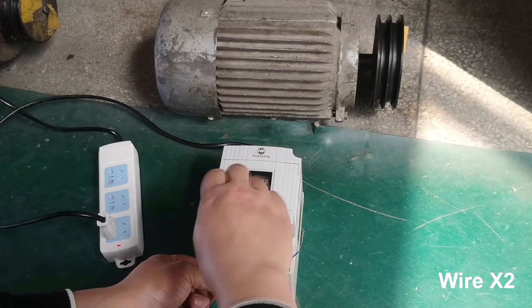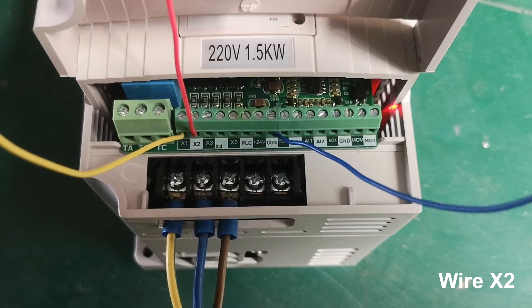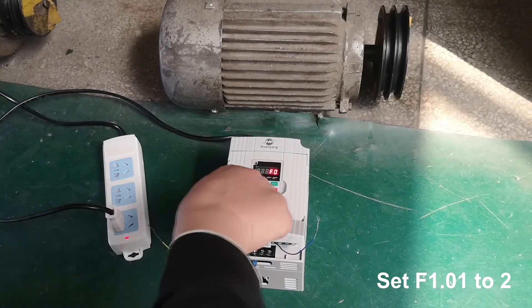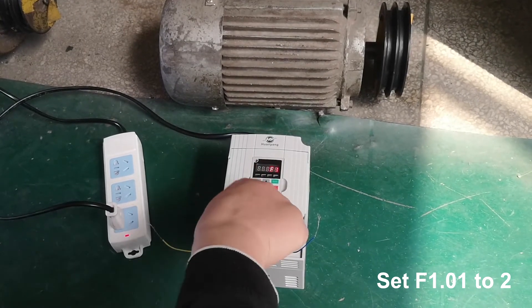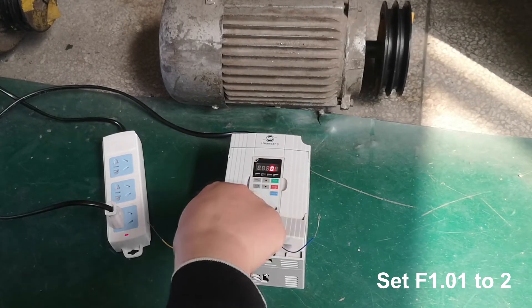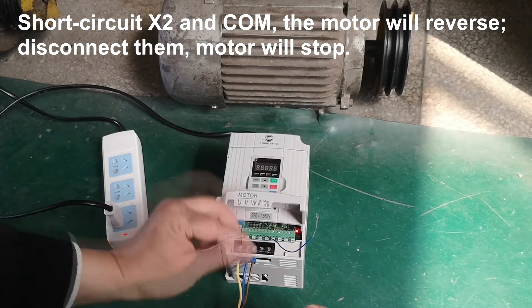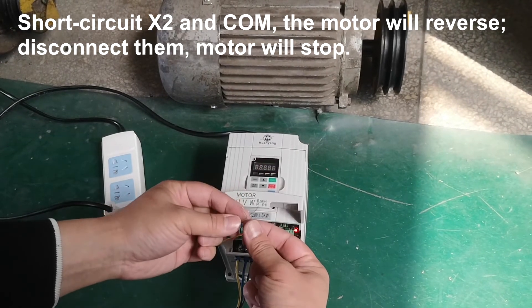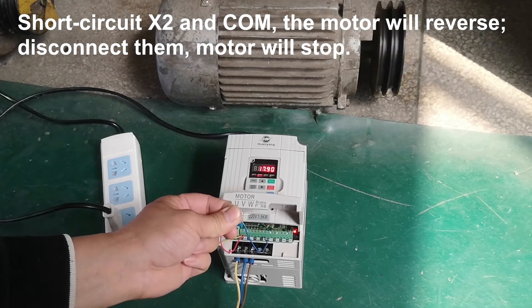Wire X2. Set F1.01 to 2. Short circuit X2 and COM — the motor will reverse. Disconnect them and the motor will stop.